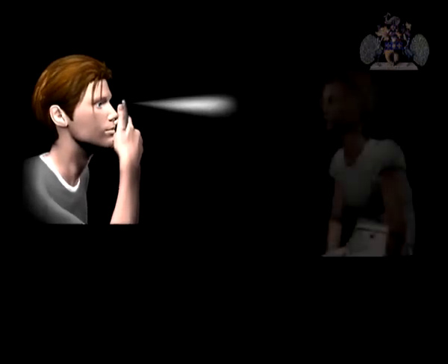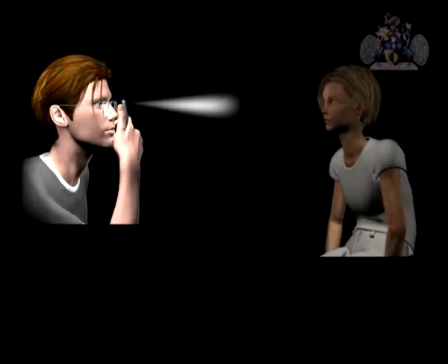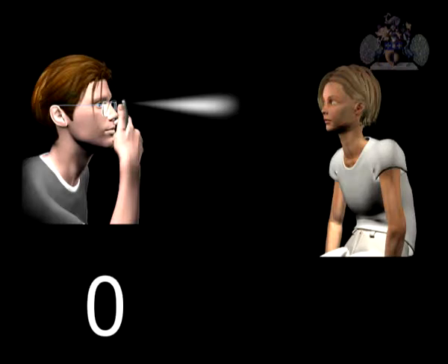If the examiner is wearing contact lenses or distance spectacles, the refractive error from the examiner's side is effectively 0. Should this be the case, the only refractive error that needs to be kept in mind is that of the patient. The examiner must remove their spectacles in order to allow adequate proximity and as wide a field of view as possible when looking at the patient's fundus.